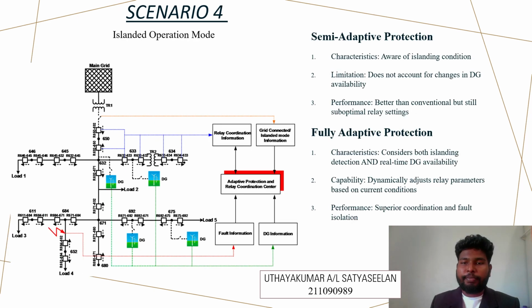Followed by scenario 4, it's about the islanded operation mode. For the islanded operation mode, there are two categories, which is semi-adaptive protection and also fully adaptive protection. So the semi-adaptive protection's characteristic is aware of islanding condition. Limitation is does not account for changes in distributed generation availability, followed by the performance, which is better than conventional but still sub-optimal relay settings. For the fully adaptive protection, it considers both islanding detection and real-time DG availability. Followed by the capability, it dynamically adjusts relay parameters based on the current condition. And the performance-wise, it's more superior at fault isolation, which is more safe.